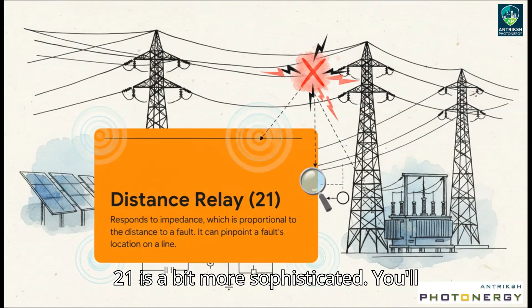So instead of just looking at current, this one measures something called impedance. Just think of impedance as electrical resistance, basically. The longer a wire is, the more resistance it has. So by measuring the impedance, the relay can actually calculate how far down the line the fault is. It's an incredible tool for pinpointing problems.